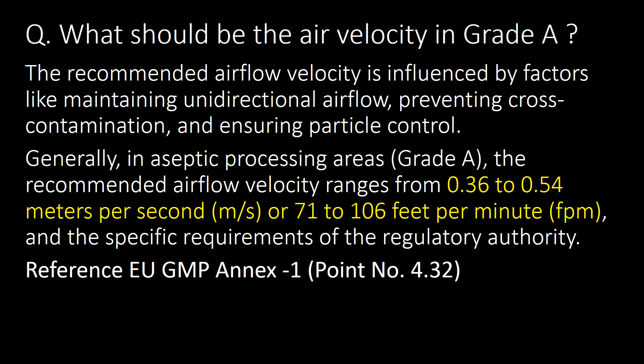What should be the air velocity in Grade A? The recommended airflow velocity is influenced by factors like maintaining unidirectional airflow, preventing cross-contamination and ensuring particle control. Generally in aseptic processing areas, i.e. Grade A, the recommended airflow velocity ranges from 0.36 to 0.54 meters per second or 71 to 106 feet per minute, as per the specific requirements of the regulatory authority. Reference: EU GMP Annex 1, Point No. 4.32.